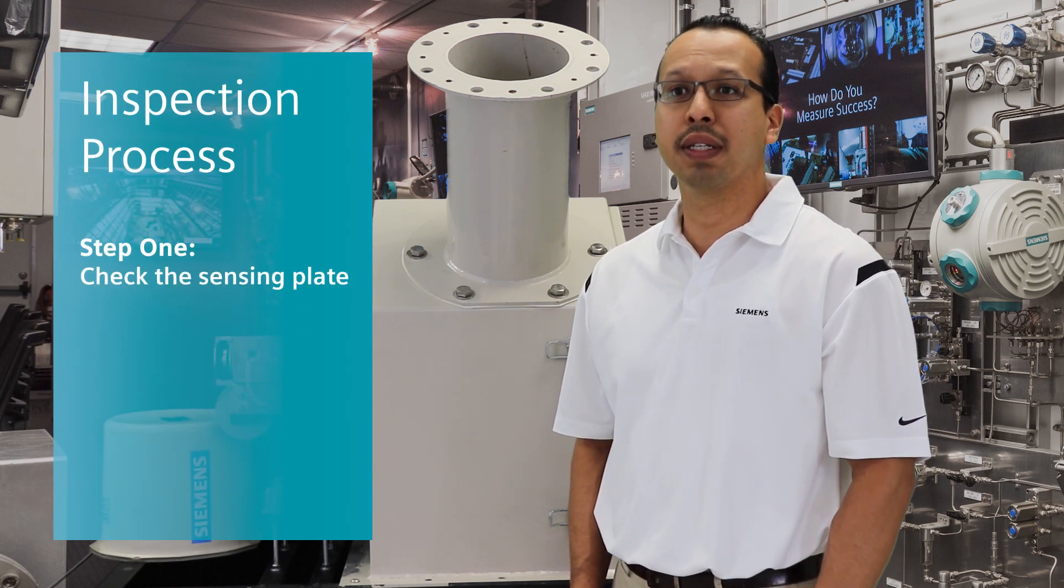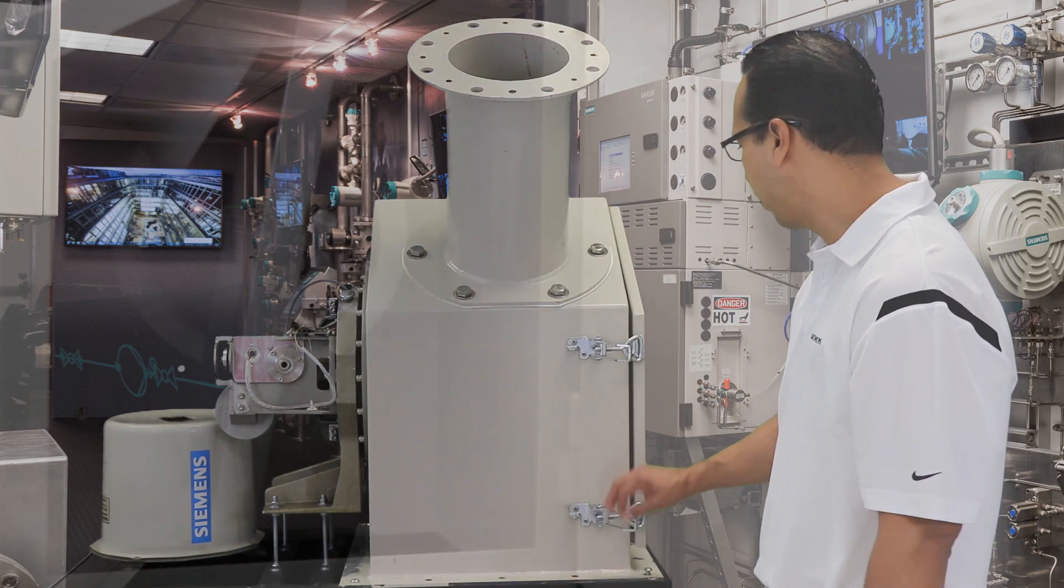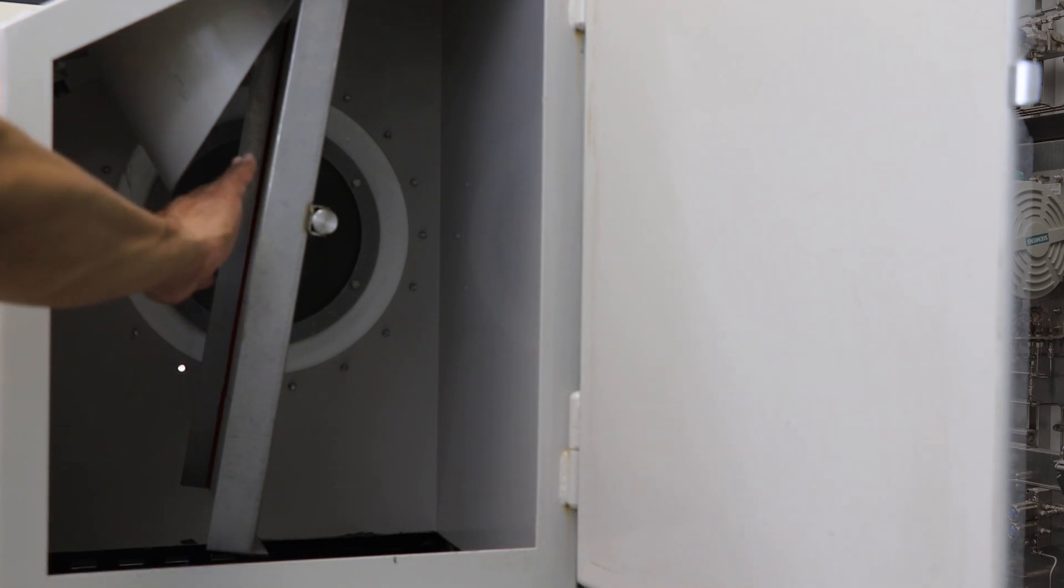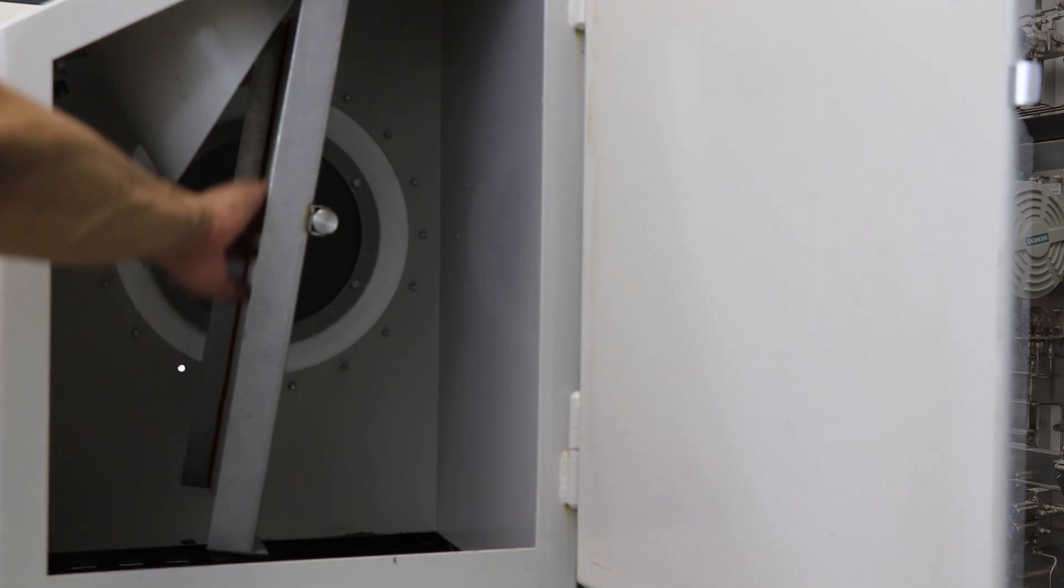The first thing we need to do is check the sensing plate. We do this by opening the doors and looking inside. After opening the door, look inside and make sure that the plate has no holes and that the liner on the plate is still intact.